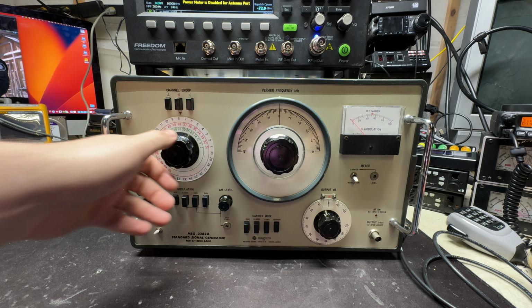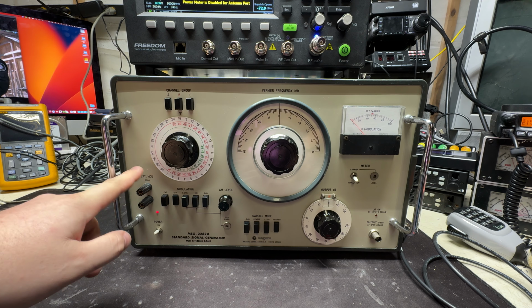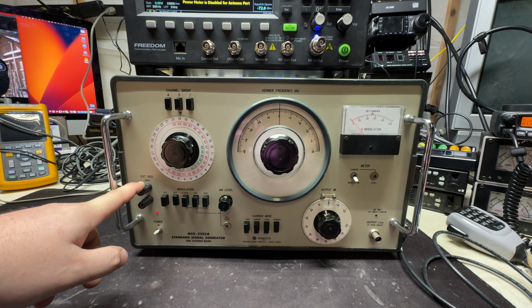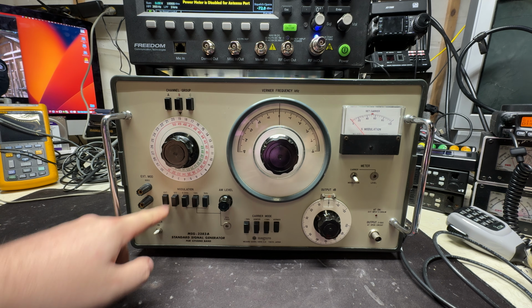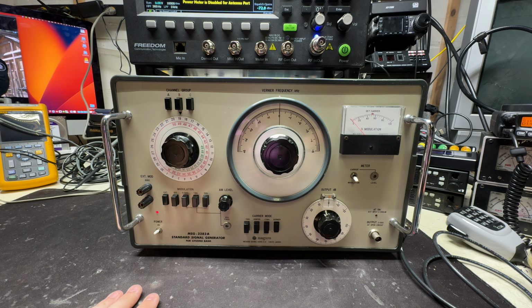Next set of buttons and dials we have here. External modulation capabilities at 600 ohms, so you could connect a microphone to the banana ports on here to modulate your own signal. You can add your own signal generator into this, like using an external audio generator. That would work fine, keeping in mind the 600 ohm, which is pretty standard to a lot of the dynamic style hand microphones, and then you would put that on the external setting here. It does have an off to turn the modulation off. You also have a 0.3 kilohertz, which is 300 hertz, 1 kilohertz and 3 kilohertz generator built into this device, so you can generate those signals, which is super handy.